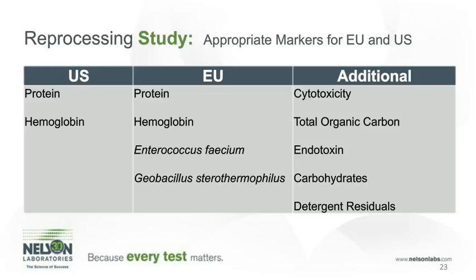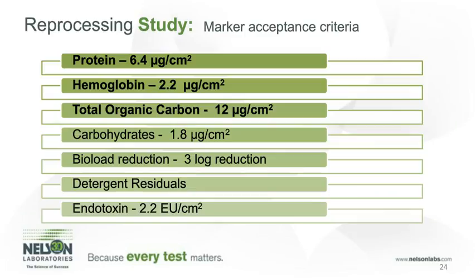Other tests that may be necessary include cytotoxicity to ensure that there are no detergent residuals left on the devices, as well as endotoxin testing if the device comes into contact with cerebral spinal fluid or brain tissue. Here are some examples of acceptance criteria for the specific residuals that may be tested. Most of these come from TIR 30 and are specific from a study from an endoscope. These are the numbers that have been accepted by the FDA for quite a while now, and if a medical device manufacturer wants to specify different acceptance criteria, they can. It's just that they need to perform testing and justification that would be appropriate to change these numbers.